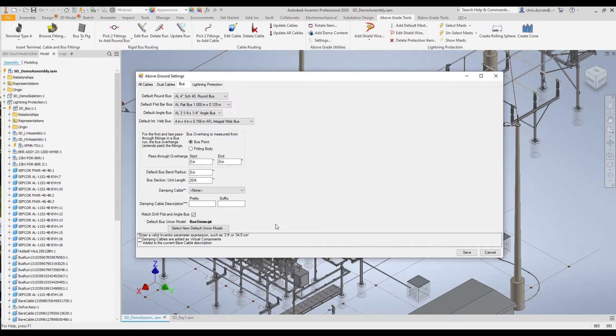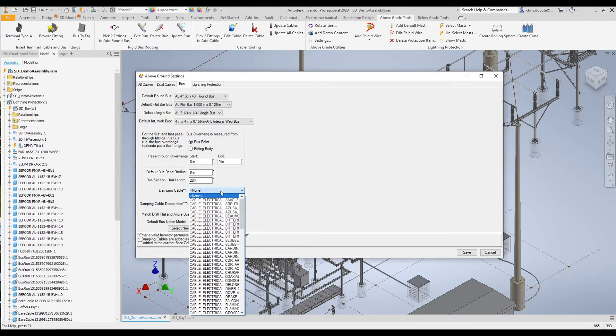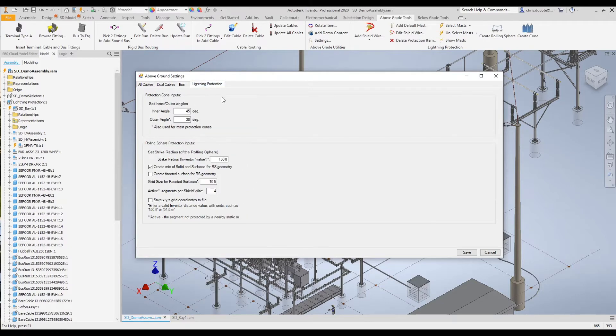We do support the creation of damping cable. The damping cable is created as a phantom part — there is no real geometry, but it will be counted in the material list if we want. For lightning protection, this is where we designate the inner and outer angles of a fixed angle or cone protection method, and right below that we'll find our rolling sphere protection inputs.